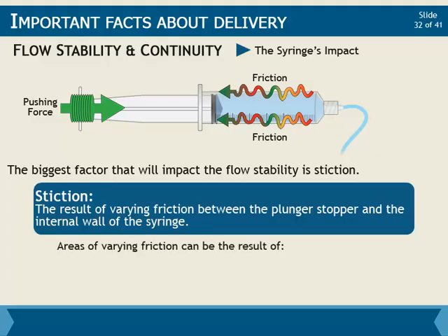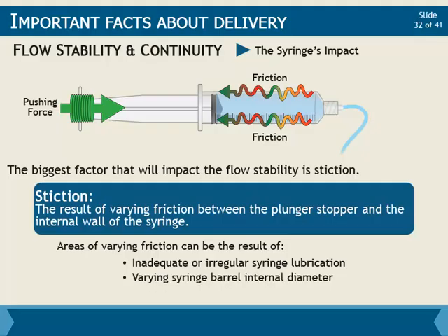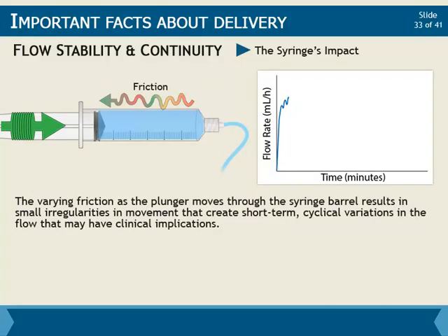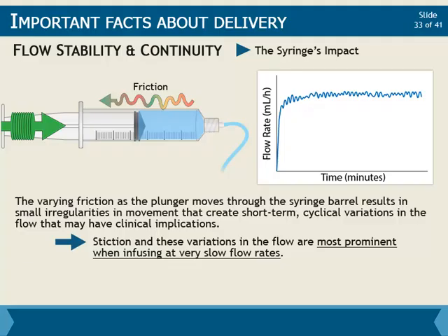These areas of varying friction can be the result of inadequate or irregular syringe lubrication, varying syringe barrel internal diameter, or imperfections with the plunger stopper material. The varying friction as the plunger moves through the syringe barrel results in small irregularities in movement that create short-term cyclical variations in the flow that may have clinical implications. Stiction and these variations in the flow are most prominent when infusing at very slow flow rates.